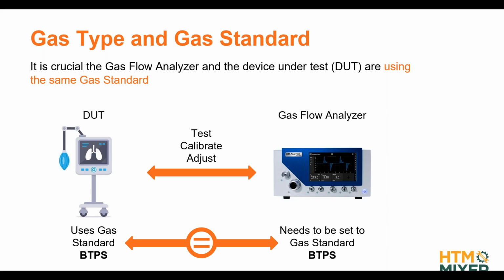BTPS, the main reason is because this is actually what ends up on a patient, but this is mainly for ICU ventilation. So in some other applications, you might not have that amount of humidification, or you might not have a heated wire. Then you probably want to compensate differently for what's ending up at the patient. And be aware that some ventilators even differentiate if you are in service mode, for example. Then there is a switch where you can set no humidification, and that actually changes the gas standard they are using. So this is really something you have to figure out. But the key takeaway is that it needs to match your device under test. Otherwise, you can easily have 15 to 20% failures.